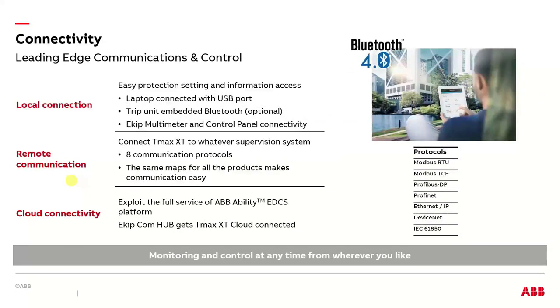And then connectivity, and that's a big jump in the solid state trip unit world, where you can hook up multiple breakers together and either poll them, sort of like a simple Modbus hierarchy, or you can even have breakers talk to each other with some of the newer protocols. For example, IEC 61850 lets horizontal communication take place, where you're doing feeder to feeder, feeder to main. So you can set up some really interesting data collection and also control when you have the breakers all communicating with each other. And then in ours, we've developed a Bluetooth module where, if you are so inclined, you can do your settings in a near field Bluetooth environment, so that you don't have to get close to the breaker to alter its settings or do what you have to with it.